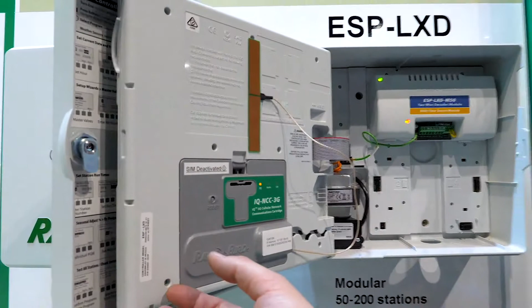So it sends 0s and 1s out to the field, and the decoder reacts off its address. The advantage is you're only running 2 wires, so you've got less wire in the ground. You can run further, and you can run more stations at once. It gives you greater flexibility, and even expanding the system, you can just extend your 2-wire path.